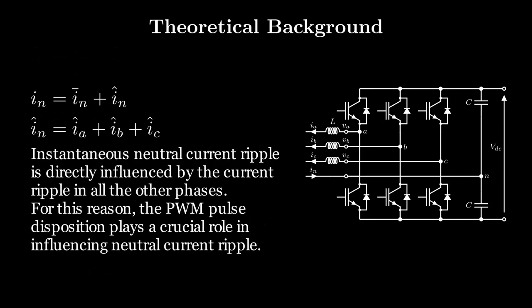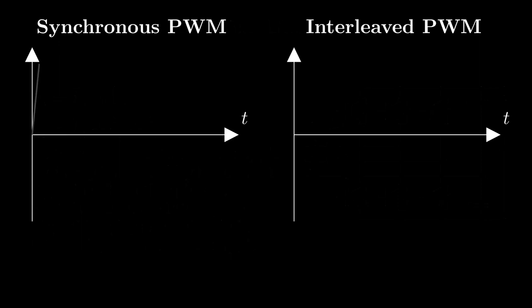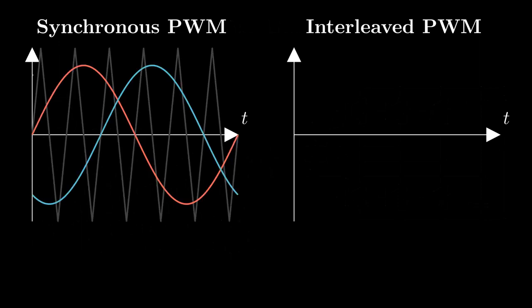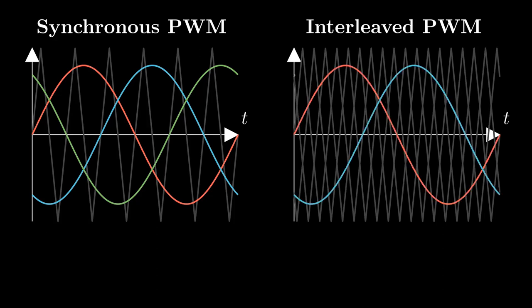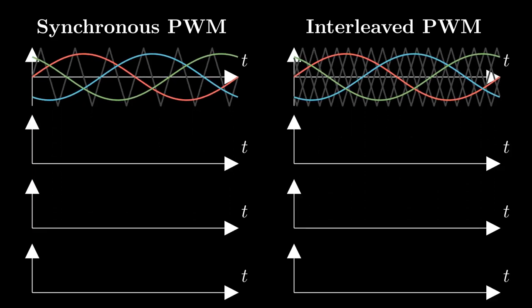Clearly, PWM pulse disposition can influence this summation in a constructive or destructive way. The two most popular PWM techniques for split capacitor inverters are synchronous and interleaved PWM. The first compares each modulating signal against a unique carrier, while the second presents three carriers associated with each phase. The fundamental AC component is the same for both techniques, but the ripple is modified by the different PWM pulse dispositions.